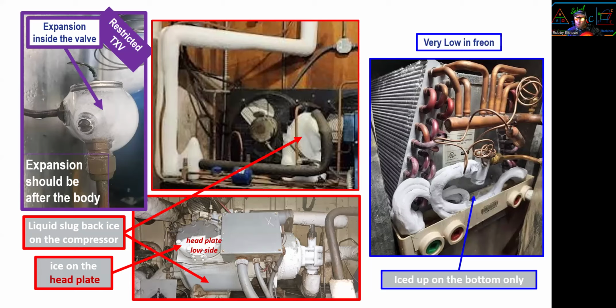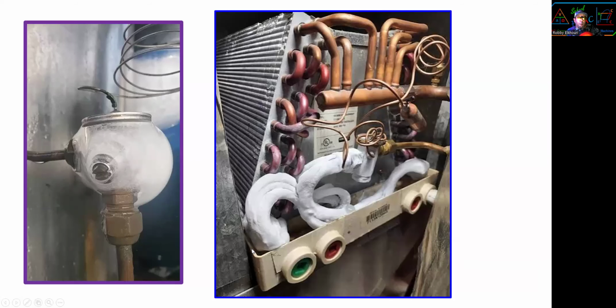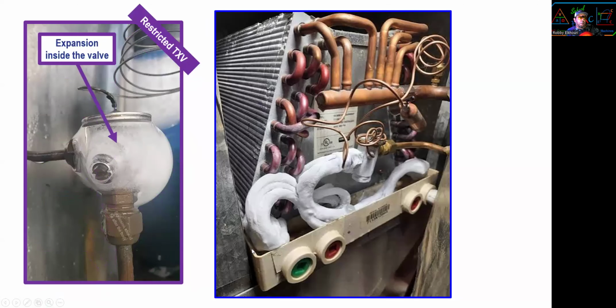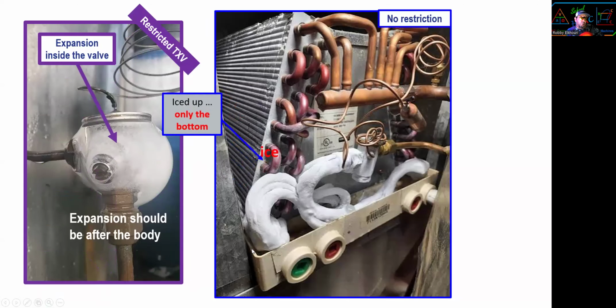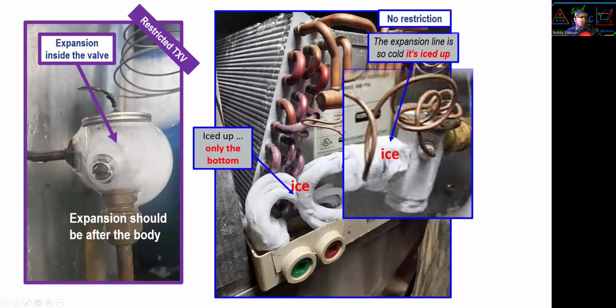Give it maybe 1 day, maybe a year, maybe 10 years, but I guarantee you it's going to fail. I guarantee you. If you see this, it's bad. No ice should be on the head of the low side. All right, now, restriction. Expansion should be at the evaporator. This one.